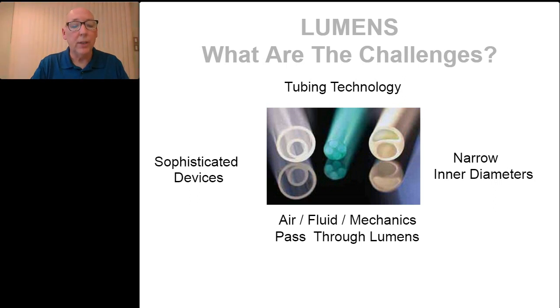Now, those narrow lumen instruments and endoscopes can be one of your biggest challenges as far as reprocessing, not just drying, but also making sure that they're cleaned properly and sterilized. Whether you're brushing, flushing, washing, or drying, they can present challenges. And they are inside the devices, limiting visual verification of processing, including drying. Great news that the industry is moving towards using borescopes to take a look down lumen devices to see what's in there as far as any debris that's left, et cetera. That's where the processes need to start moving forward with those types of devices so that you can see inside those lumens.